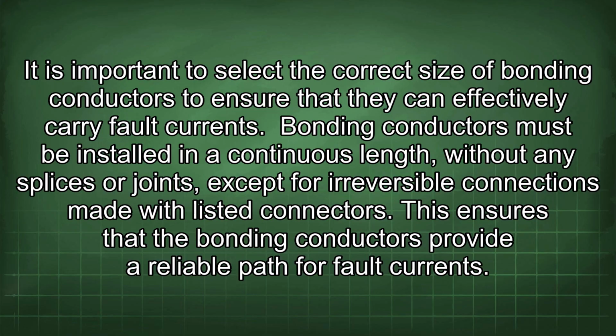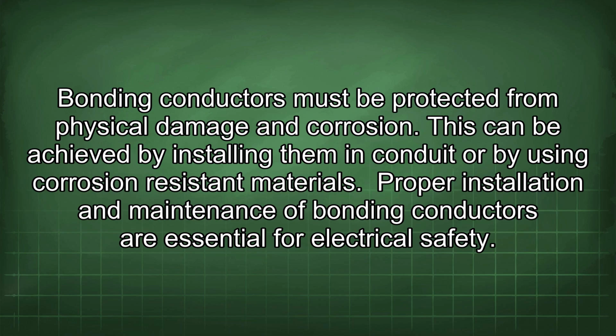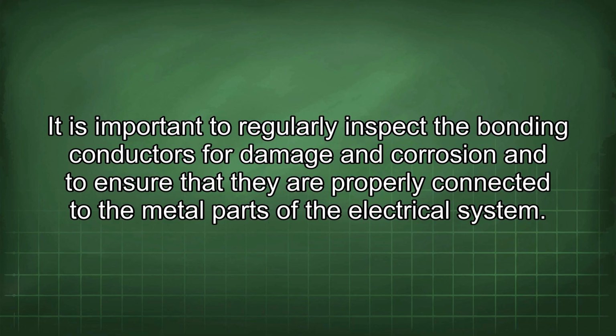Bonding conductors must be installed in a continuous length, without any splices or joints, except for irreversible connections made with listed connectors. This ensures that the bonding conductors provide a reliable path for fault currents. Bonding conductors must be protected from physical damage and corrosion. This can be achieved by installing them in conduit or by using corrosion-resistant materials. Proper installation and maintenance of bonding conductors are essential for electrical safety. It is important to regularly inspect the bonding conductors for damage and corrosion and to ensure that they are properly connected to the metal parts of the electrical system.